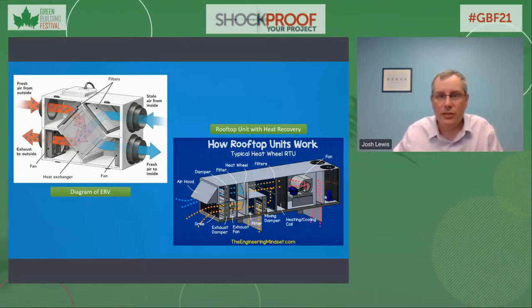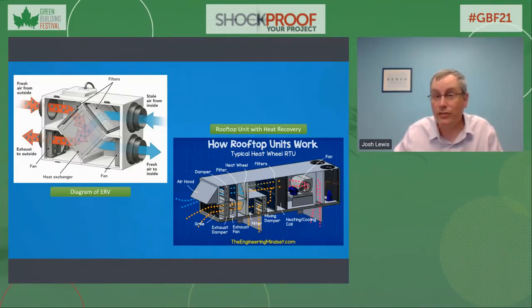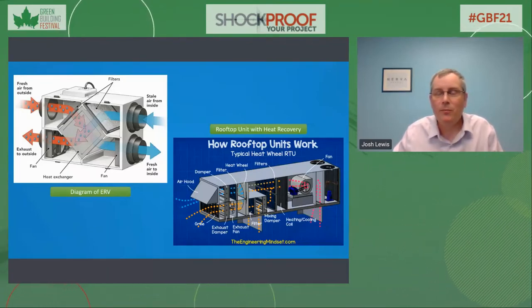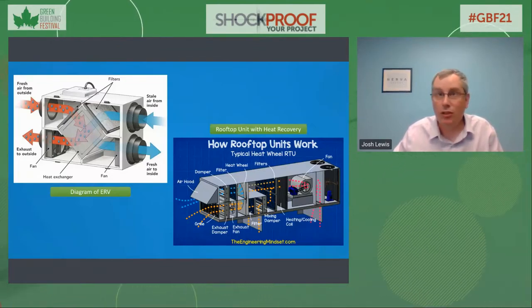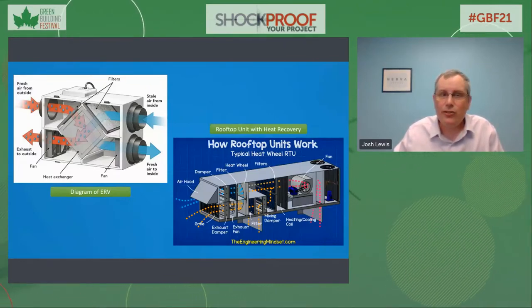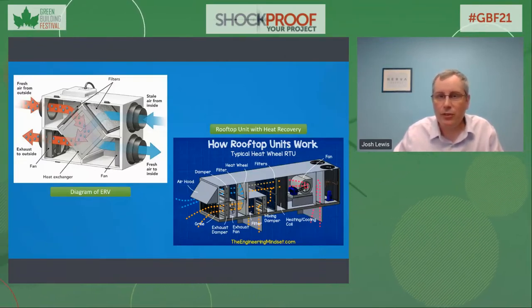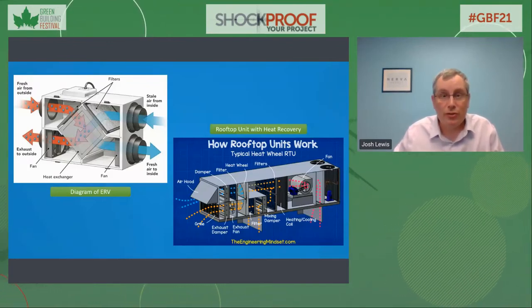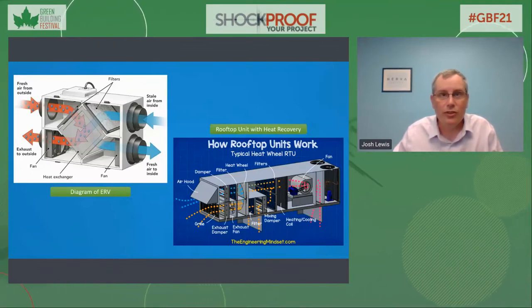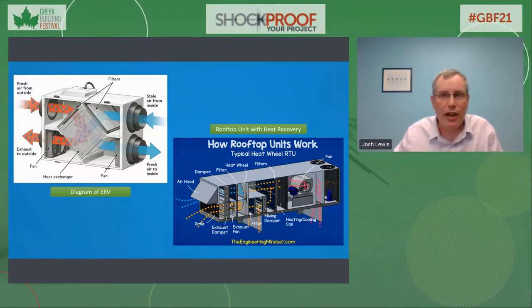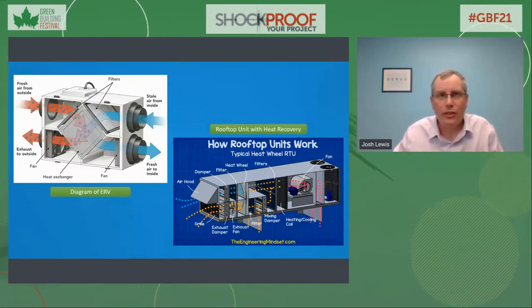HRV and ERV systems come in many forms and utilize different types of heat exchange mechanisms, from metallic cores to wheels to semipermeable membranes, and even paper. Their overall purpose is to capture the energy from the air leaving the building, both in the form of temperature, also known as sensible energy, and humidity, also known as latent energy, and then give up that energy to the air coming into the building, with typical equipment efficiencies ranging between 50 to 90% recovery. By using these systems, more fresh air can be brought into the building with much less of an impact to total energy usage. This has a positive impact on both the indoor and outdoor environments, and can go a long way to improving indoor air quality without creating a massive spike in energy use.